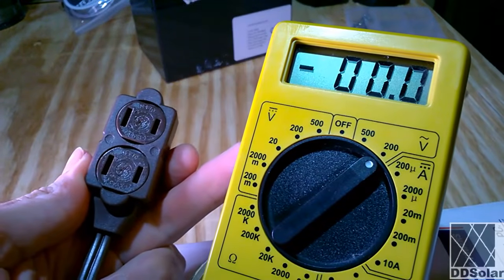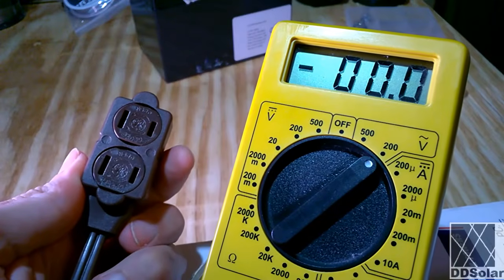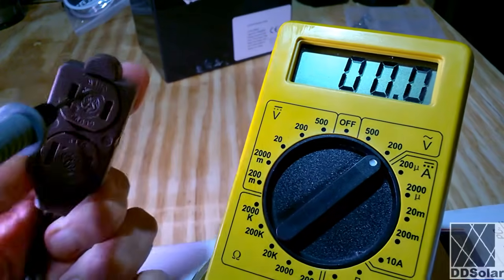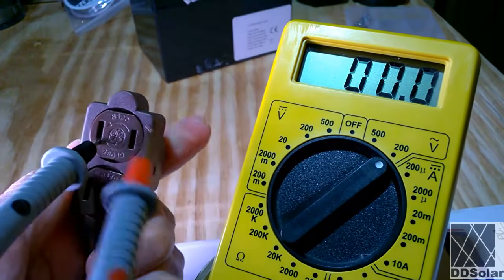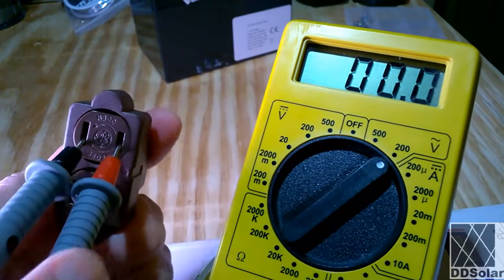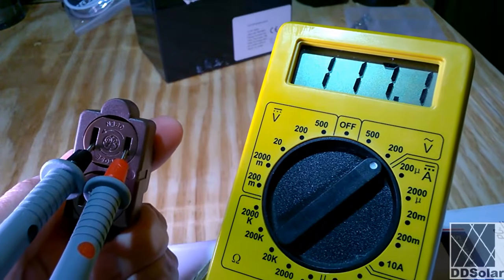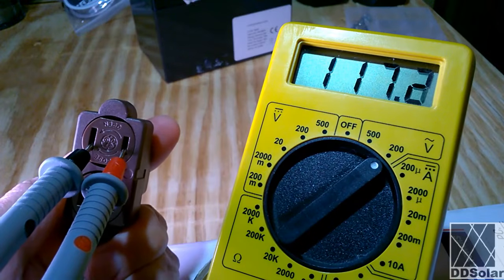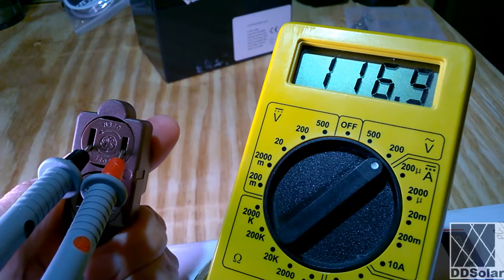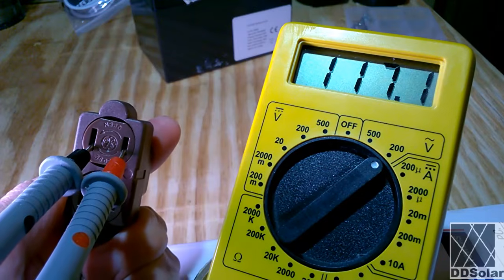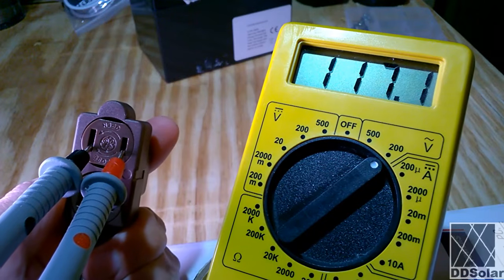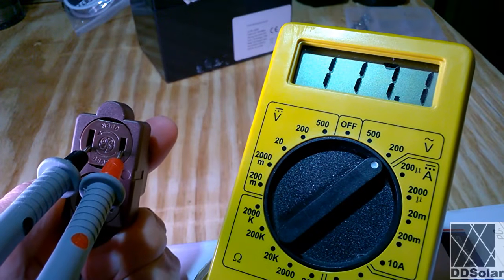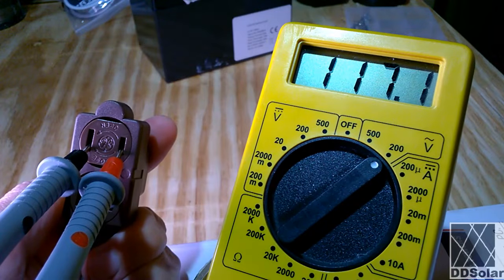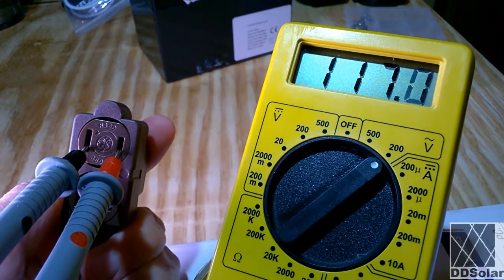You can see that we now have a single decimal point, which for AC is kind of overkill, but in this case we're measuring the household power, so we really don't need a decimal point. But as you can see, 117.1 volts. So once again, that's a good reading. That's more or less what I would expect. And a really interesting use of a meter like this is you can plug your meter into a circuit and then turn on an appliance and see how much voltage drop you get on that same cord.